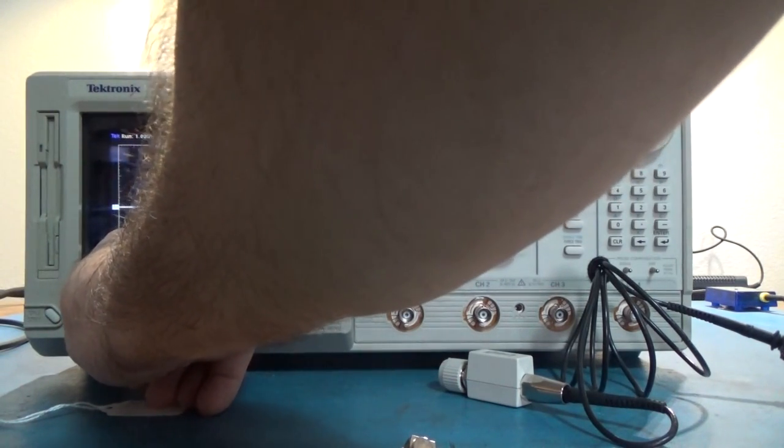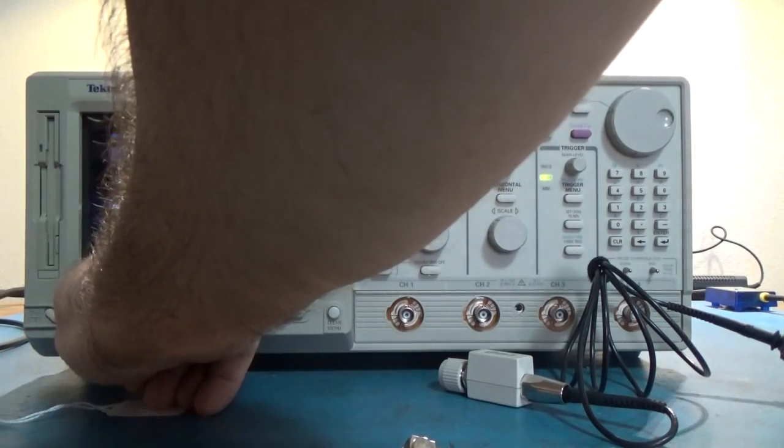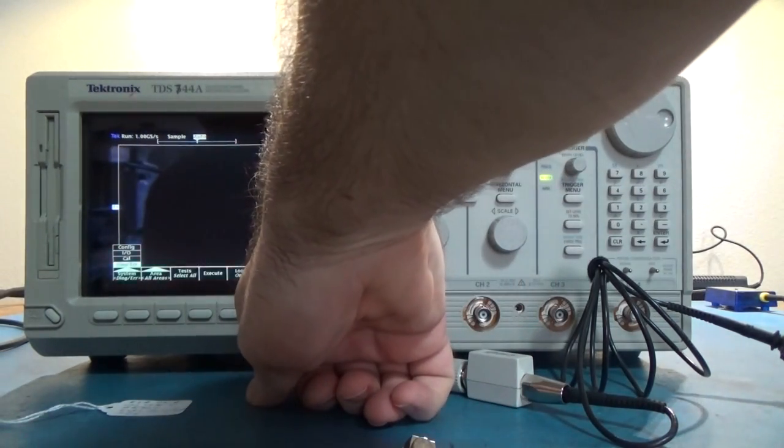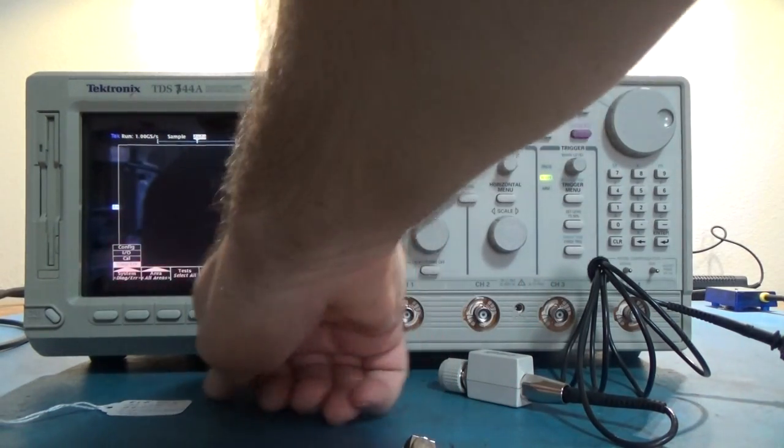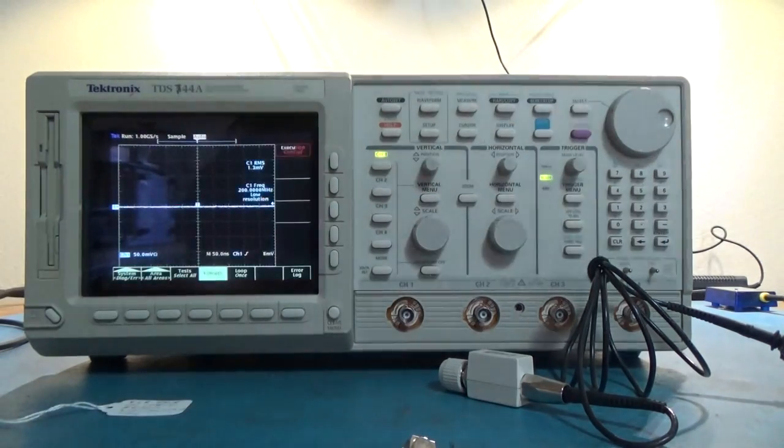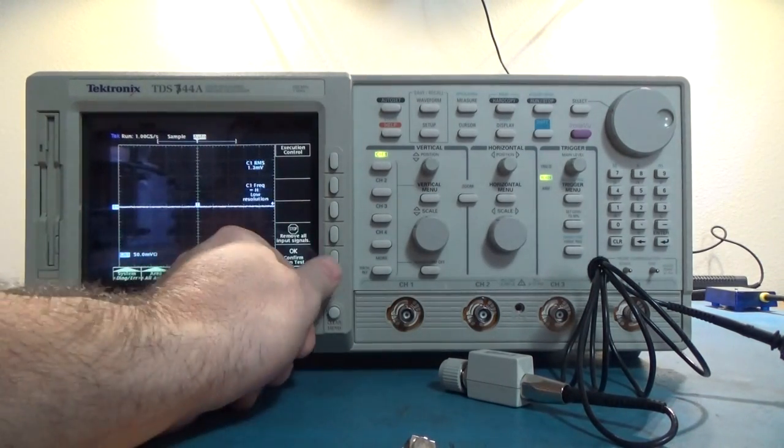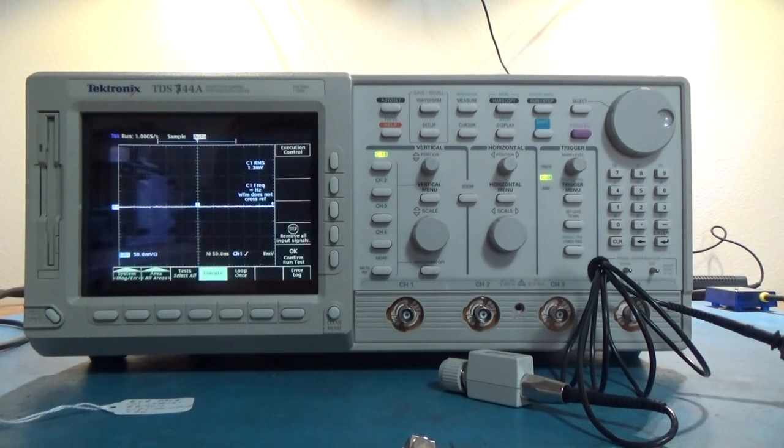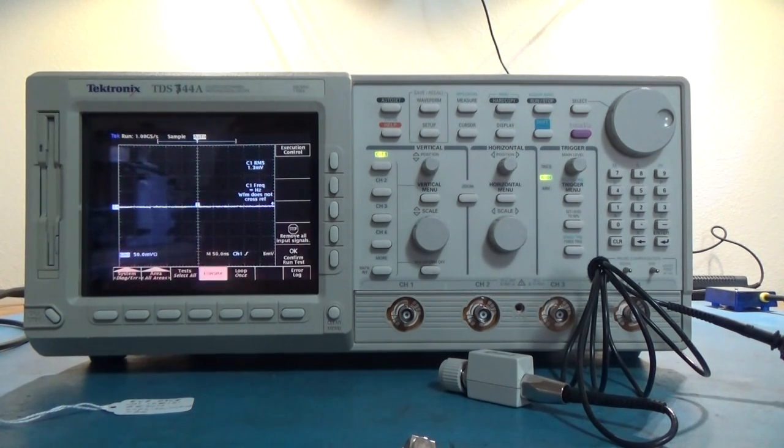If you're plugging in an active probe and you're kind of screwing with it, you'll get some probe errors. Who cares? You'll just clear the error log. There's plenty of information out there about the error log. And how to deal with it. So you'll send the error log clear command with your GPIB. The scope should be able to get through all of the self-tests.